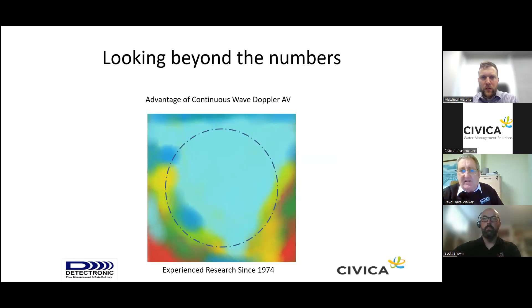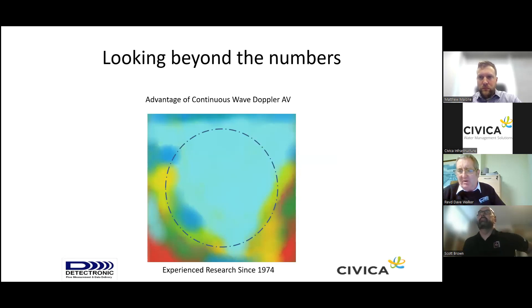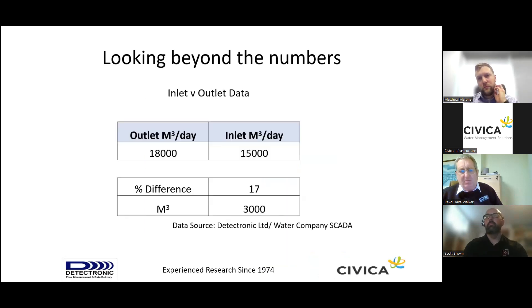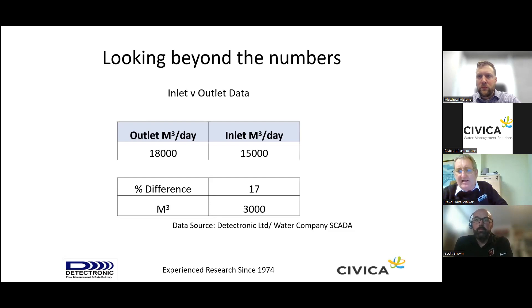The advantage of continuous wave Doppler is that it spreads out on an actual trajectory, sitting right in the middle of the velocity profile in the channel. On that particular site, we were getting 18,000 cubic metres coming out of the outlet but only 15,000 cubic metres per day coming into the inlet — which in itself revealed the errors in the hydraulic profiling. This was an effect of the Bernoulli principle, which was also creating pulsating flow and velocity spikes, where the velocity was increasing and decreasing in a pattern that was not consistent with pumped flow.